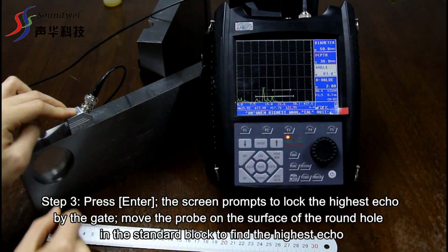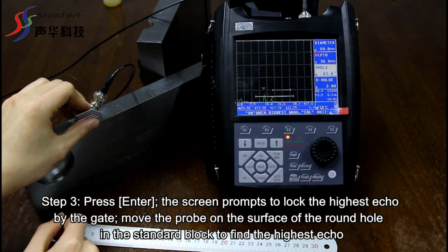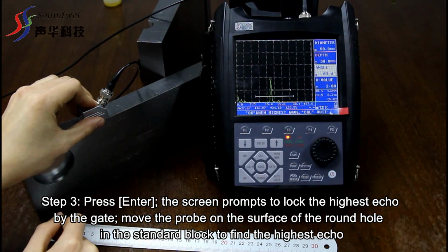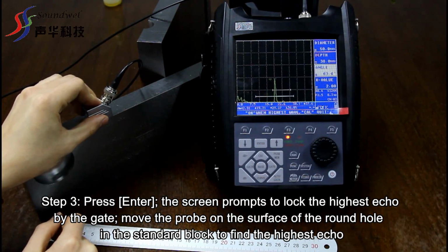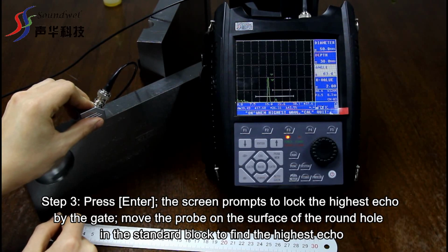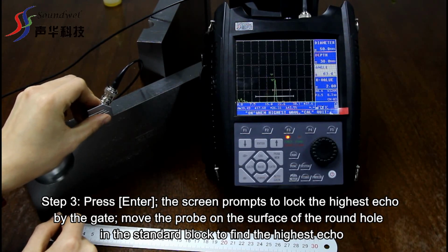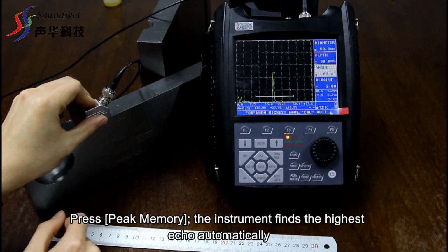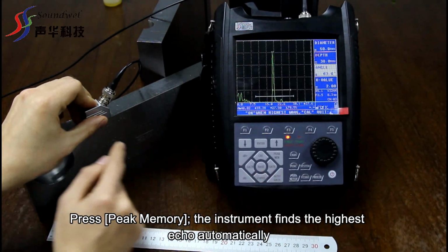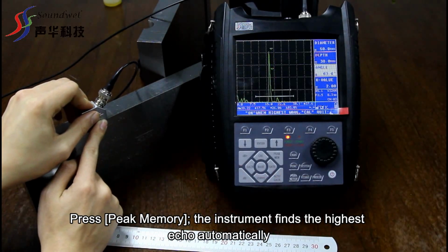Step 3. Press Enter. The screen prompts to lock the highest echo by the gate. Move the probe on the surface of the round hole in the standard block to find the highest echo. Press Peak Memory. The instrument finds the highest echo automatically.